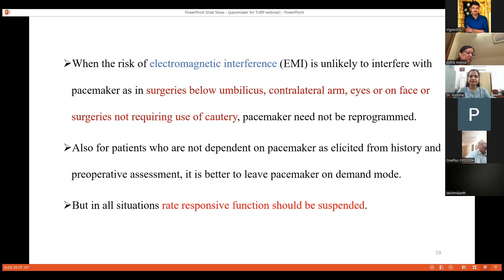Also, for patients who are not dependent on the pacemaker, as elicited from the history and preoperative assessment, it is better to leave the pacemaker on demand mode. But in all situations, the rate responsive function of the pacemaker should be suspended. How will you reprogram it, if you have to reprogram the patient's pacemaker? It can be done either by magnet or reprogramming software.